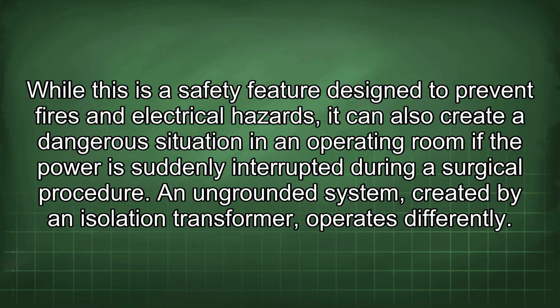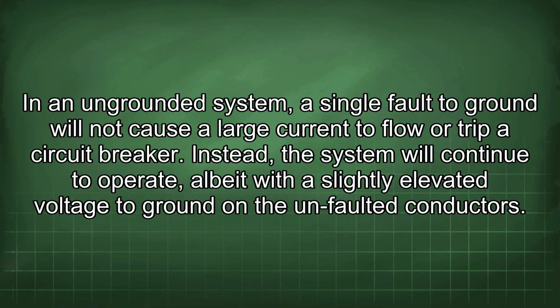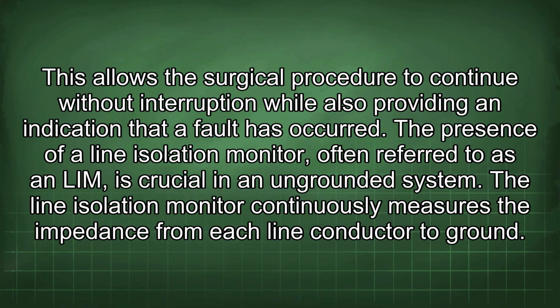An ungrounded system created by an isolation transformer operates differently. In an ungrounded system, a single fault to ground will not cause a large current to flow or trip a circuit breaker. Instead, the system will continue to operate, albeit with a slightly elevated voltage to ground on the unfaulted conductors. This allows the surgical procedure to continue without interruption while also providing an indication that a fault has occurred.